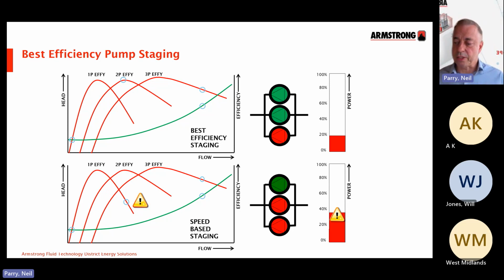But what I'm showing here in the graph is pumps have operating points where they're running at their most efficient. And what Armstrong do with our pumps is we test every single pump before it leaves the factory. When we do that, we're able to map flow and head and shaft rotation speed and power draw into the pump intelligence itself that's built in to every pump. When we do that, we now know at what point that pump is running at its highest efficiency. So what we can see here on this top graph is we're using 3 pumps, and this is the pump efficiency curve, the red line, and you can see it peaks and then starts to drop off significantly. Now that peak generally tends to be somewhere around 60% of capacity.